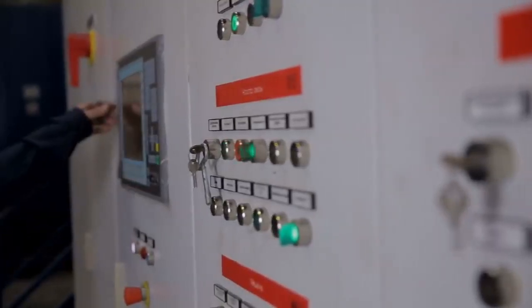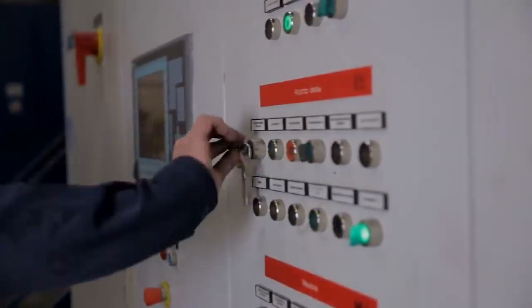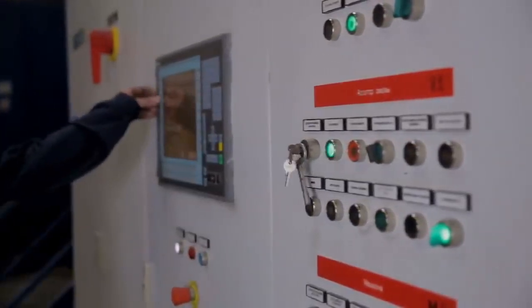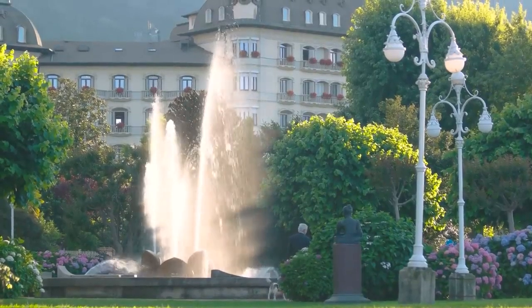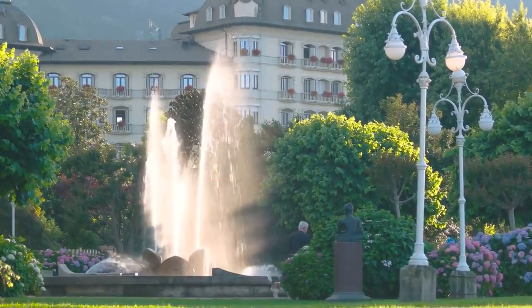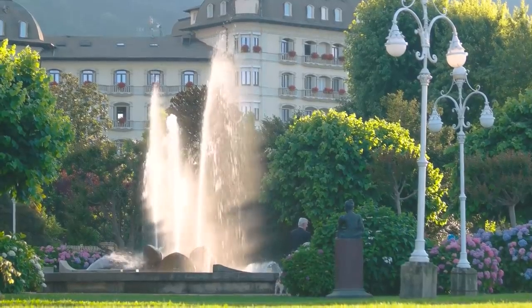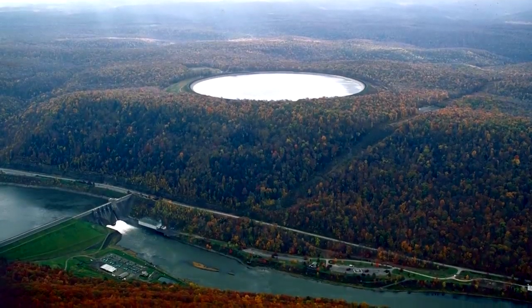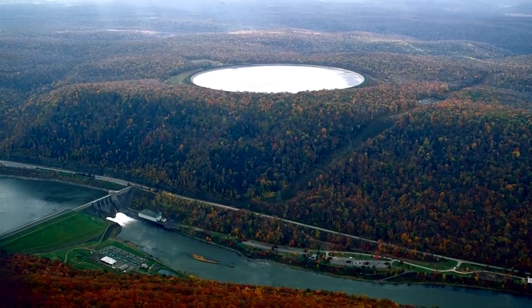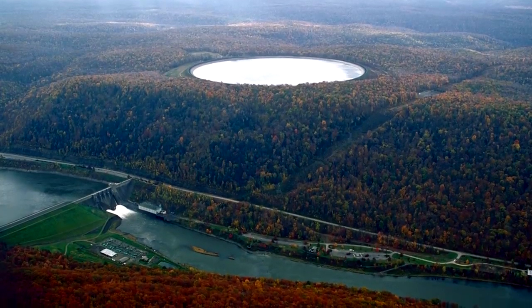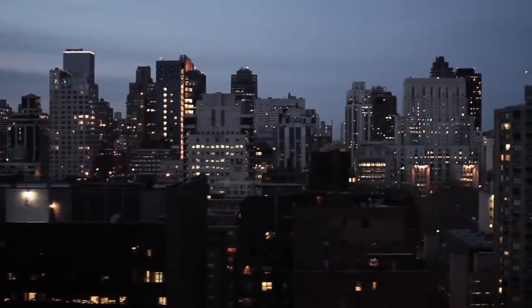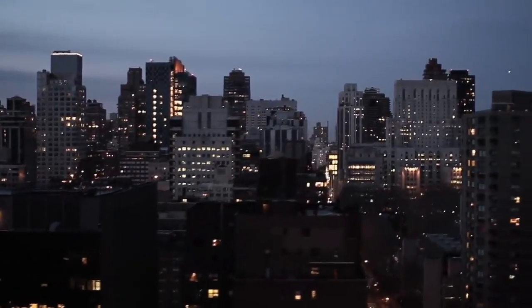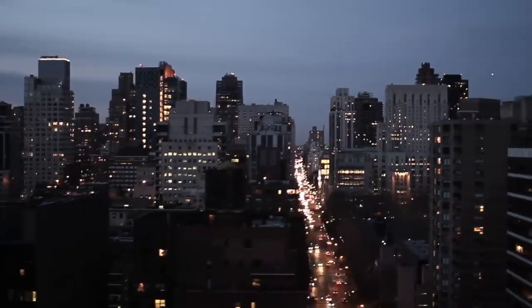In some areas where electricity costs vary based on demand, you can run the pumps at night when electricity is cheap to fill up your water tower, then leave the pumps off during the day when electricity is more expensive, allowing just the tower to pressurize the system and serve your customers. Storing energy this way is also carried out at a larger scale to help with electrical grid reliability, but that's a topic for another video. Elevated storage is also beneficial during a power outage by keeping the system pressurized even when the pumps are out of service.